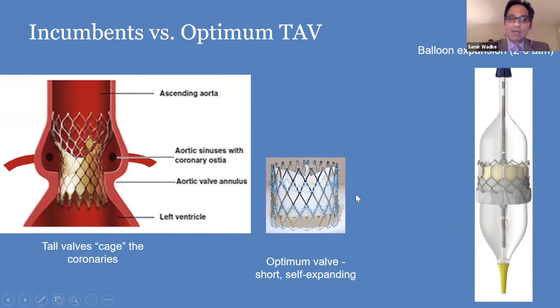What's required is a short but self-expanding transcatheter valve with no further design limitations. That's exactly what our Optimum TAV is. It was designed after the natural valve. It's also about 2 centimeters tall. In addition to avoiding the design limitations I mentioned, it also has no suture holes in the flexion zone, or the moving part of the leaflet, unlike most transcatheter valves. As we've learned from the 50-year history of surgical valves, a single suture hole in the flexion zone can promote calcification and wear and tear of the leaflets. And so our valve is designed much more like a surgical valve in that sense.